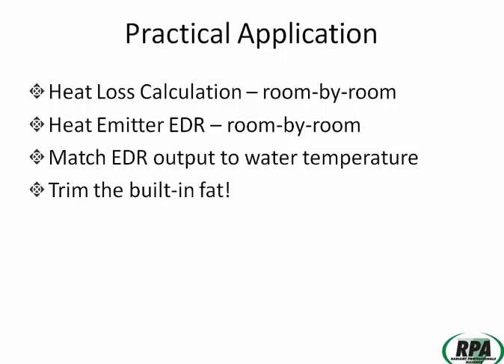Go ahead, Mark. And we want to trim all that built-in fat. Every program that we use to calculate heat loss and heat gain calculations, and also for sizing circulators and systems and pipe sizing from start to finish, has a lot of built-in fat. It's been our experience that that runs anywhere from 10 to 30% over what our best calculations show. Next.